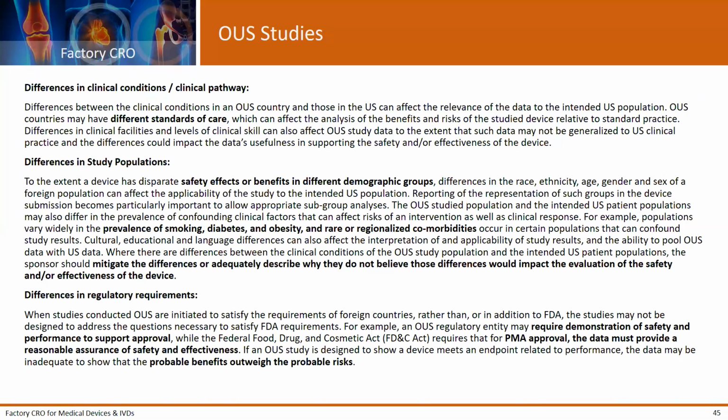In general, what I tell clients is that although you're not required to have a complete quality system in place prior to conducting a clinical study, you're certainly going to want to have control of documents. You're going to want to have design controls in place before you launch a product, because you want to release it internally and say it's okay to release that product for the clinical study.